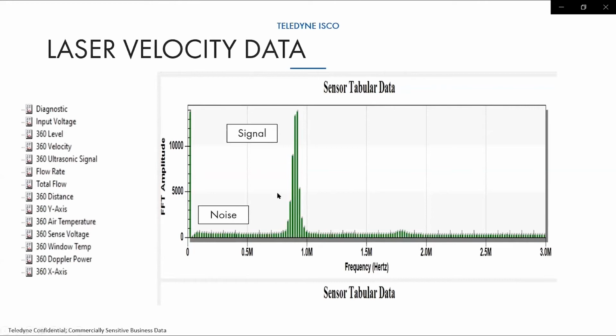Other diagnostics that are available to you, especially on the LaserFlow we're seeing here, we've got ultrasonic signal strength. We already talked about that. It'll tell us the distance to the surface of the water, which is easy to measure. We can read the X and Y axis, so that's going to tell us if the sensor is still level in that application. And when you want to look at that, say maybe after the sensor is submerged, instead of just sending somebody out there immediately, you can look at these.